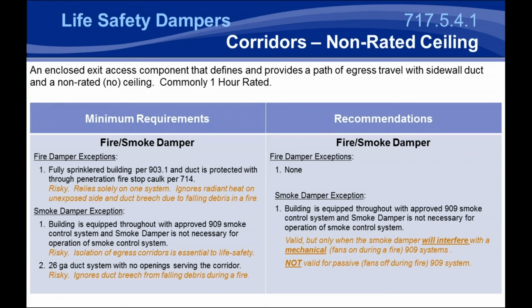Basically, you've got a fully sprinklered building and the duct is protected with fire stop caulk per section 714. You can remove the fire damper requirement, but we feel this is risky. And the main reason we feel this is risky is because there's no limit to that fire stop caulk, and you don't have that duct breakaway type connection that'll make sure the penetration is protected if there is falling debris in a fire. Of course, there is a smoke damper exception if you've got a 909 smoke control system and the smoke damper is not necessary for the operation of that smoke control system.